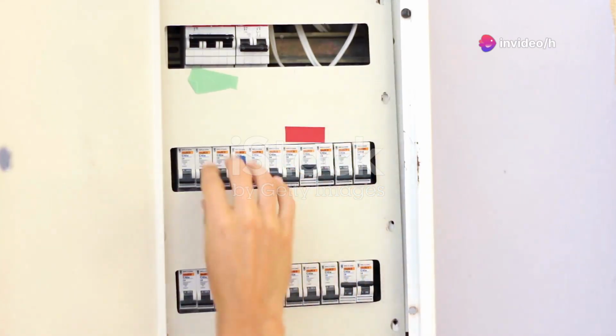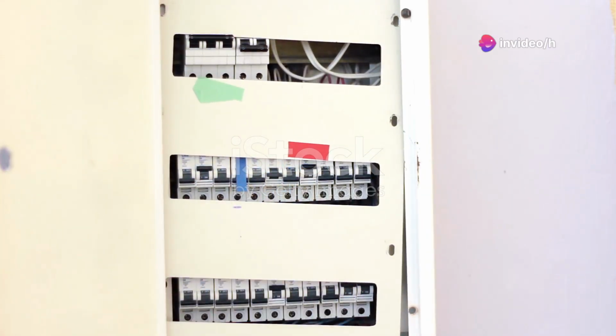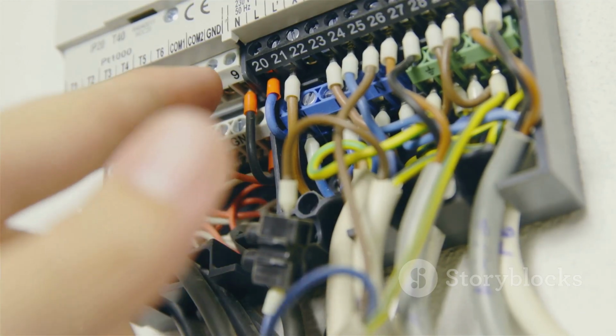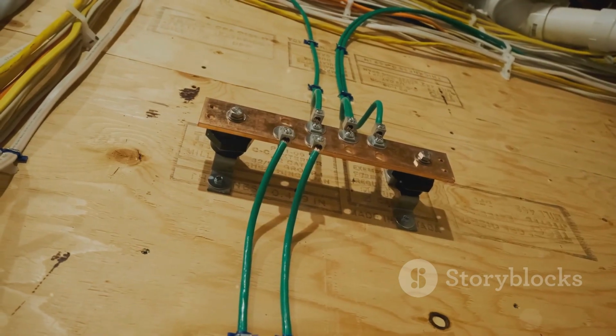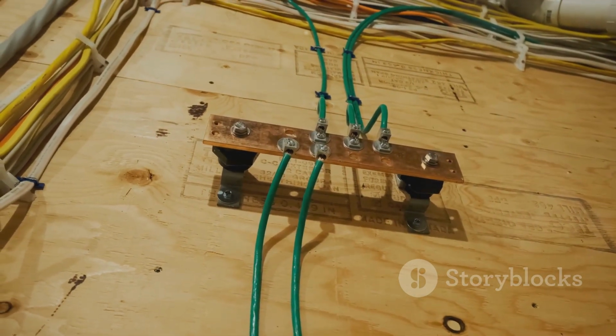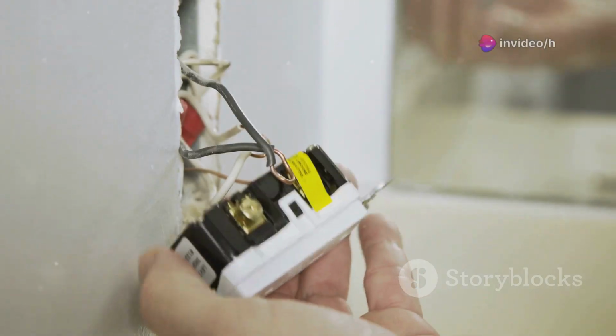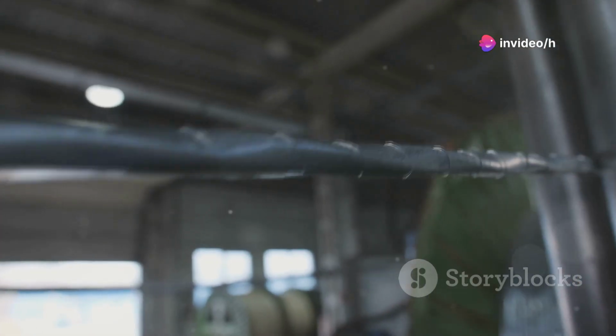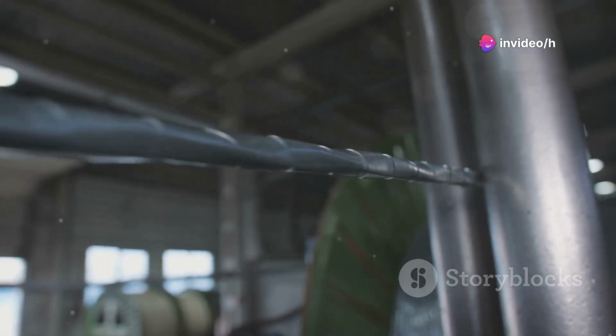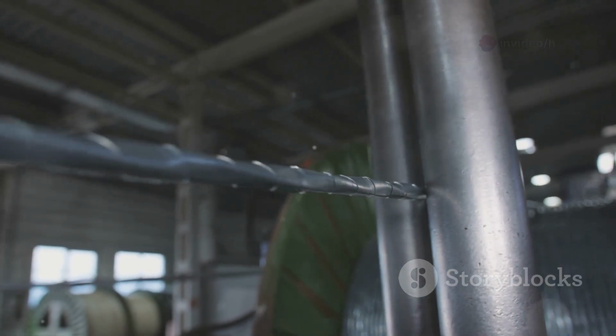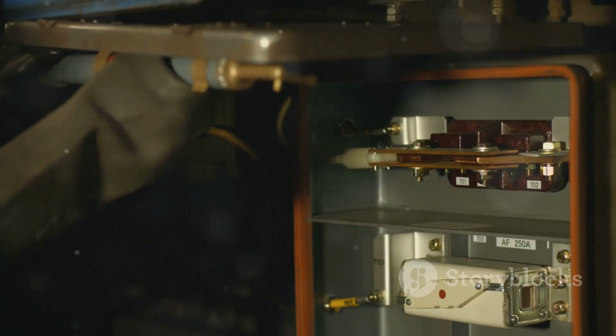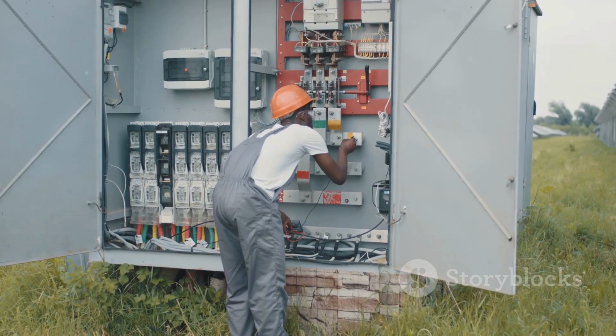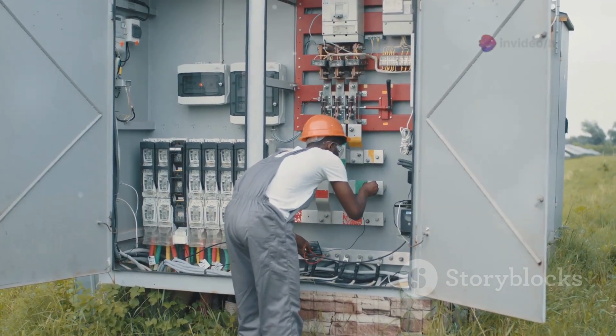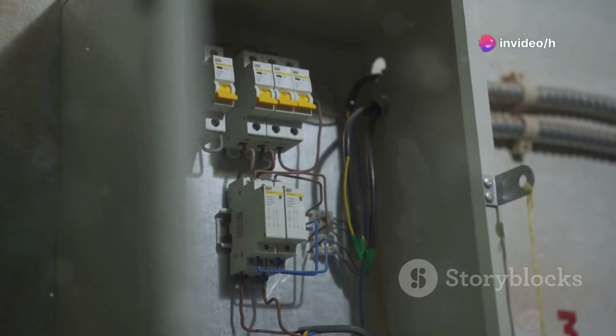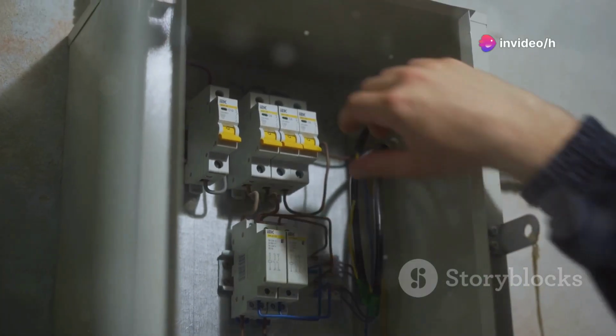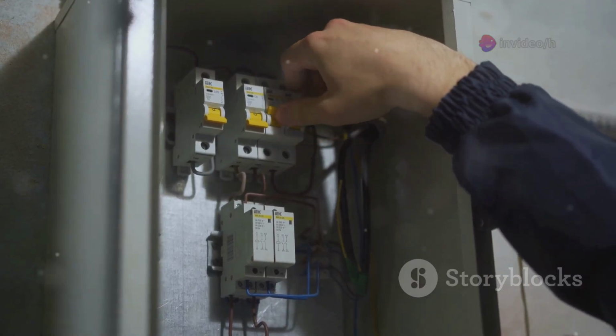Inside your main panel, the neutral wire connects to a neutral bus bar where all the white wires from your circuits return. The ground wire, bare copper or green, connects to a separate ground bus bar. The ground wire's job? Safety. It normally carries no current, but if something goes wrong, it provides a safe path for stray electricity to reach the earth. In the main panel, the neutral and ground bars are bonded together, linking your system to a grounding rod outside. This bond ensures your entire electrical system is referenced to the earth, protecting you from shocks.